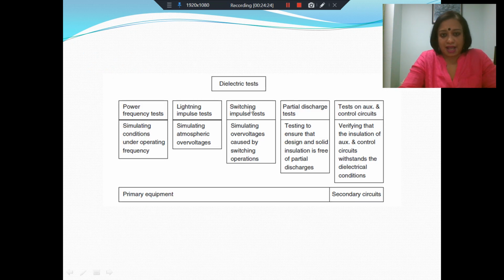If we look at the dielectric test, the principal dielectric tests that we need to do on gas insulated substations are power frequency tests. Power frequency test should simulate conditions under operating frequency and test for the various kinds of dielectric withstands. Lightning and impulse test, for which we would need to simulate atmospheric overvoltages. We know what kind of voltages to expect, what are the IEC test standards.